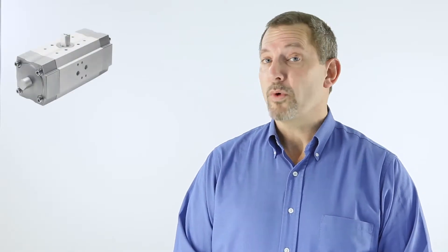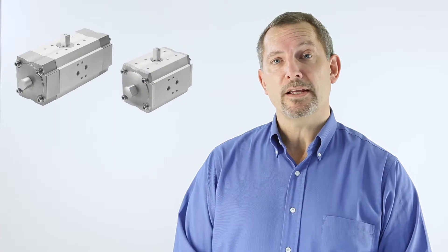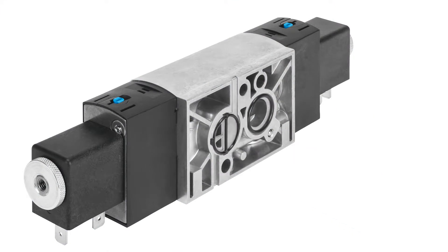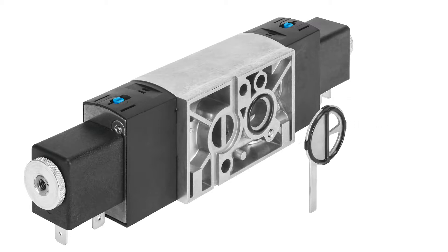Like every other solenoid valve, the VSNC consists of a basic valve and coil. But whether you are using a single or double acting actuator, we can offer you a solution with just one valve. By simply rotating the seal on the NAMUR interface, you can switch quickly between 3/2 and 5/2 valve functions as and when you need.